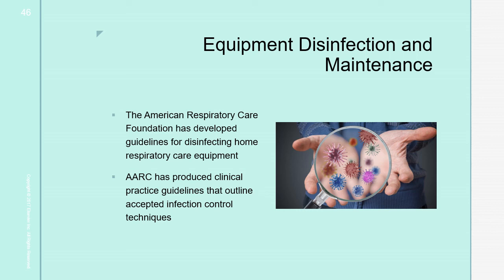About medical equipment suppliers, the guidelines suggest that all permanent equipment, like ventilator circuits, oxygen delivery equipment, and aerosol systems, be sterilized or receive high-level disinfection before being supplied to another patient. Disposable or single-use patient equipment must be used by one patient only. It's recommended that all equipment be completely disassembled and washed first in water, followed by a soak in warm soapy water for several minutes, with the equipment scrubbed as needed to remove any remaining organic material, such as secretions. Following this step, the equipment must be thoroughly rinsed to remove any residue of soap and drained of excess water. Air drying on a clean surface or rack is recommended, like a paper towel.